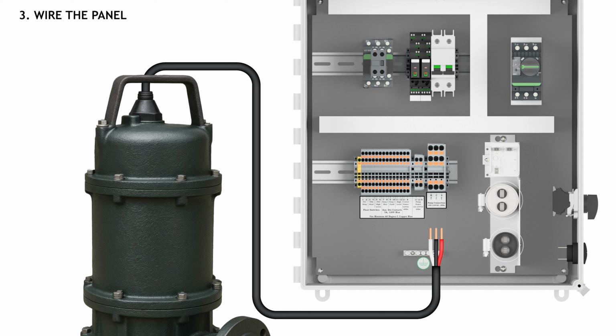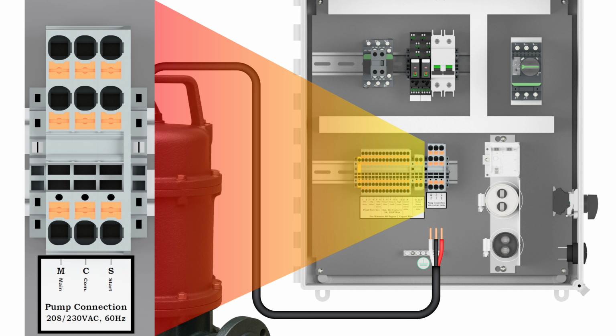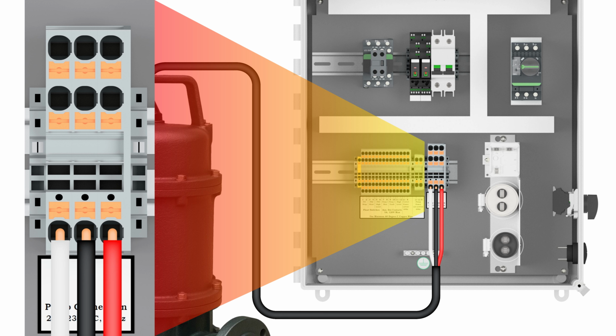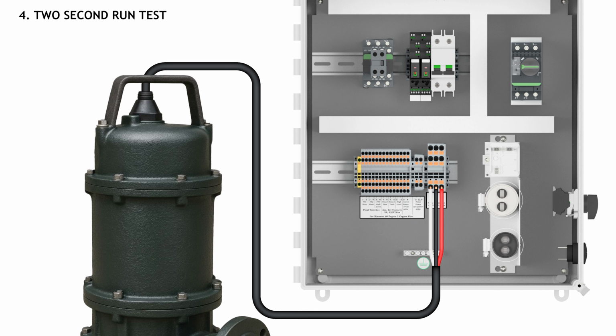Step 3. Now that we have confirmed the pump wire colors with each associated winding and also have identified the correct pump winding terminal blocks in the control panel, then wire the pump correctly to the control panel. Step 4. We are now ready to power up the pump for a 2-second run test using a clamp-on digital amp meter. First, connect power to the control panel and turn on pump control and alarm breaker if they are provided, and the pump circuit breaker.